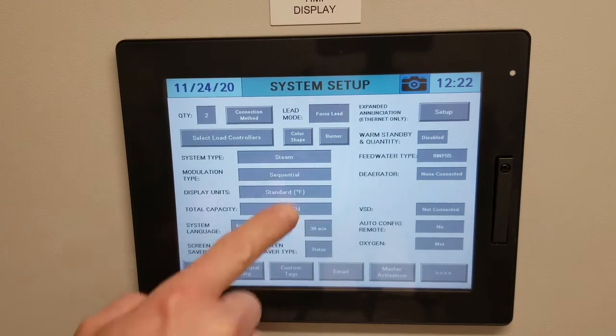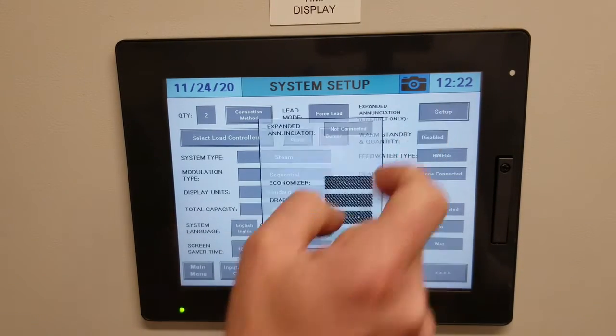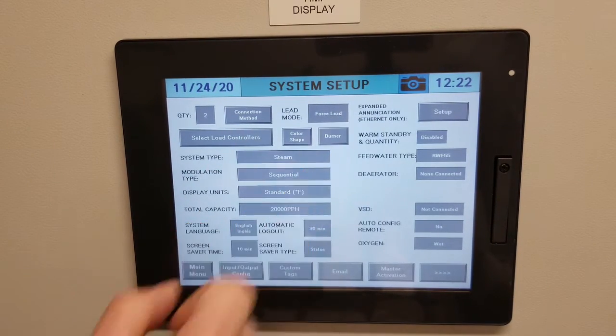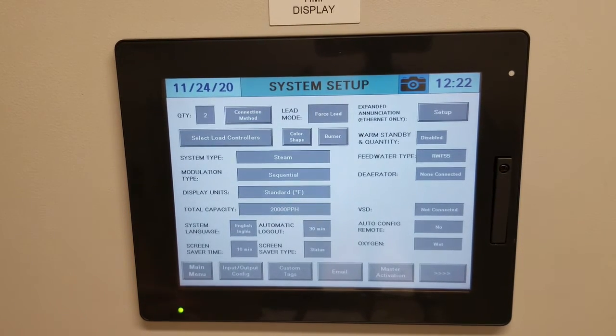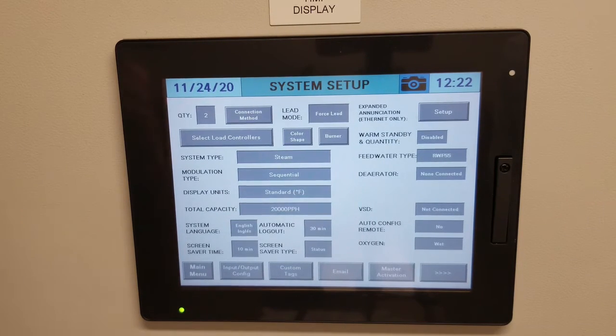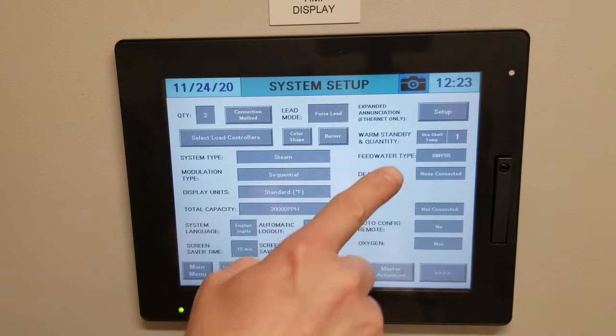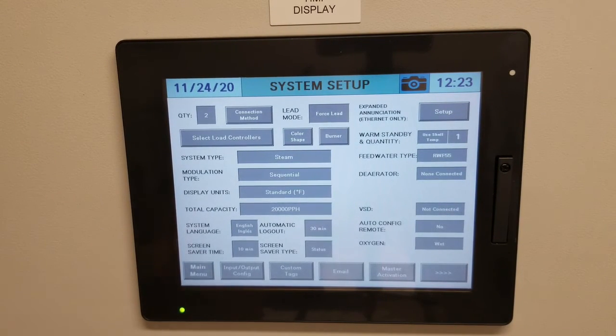On the right-hand side you'll notice an option for Expanded Annunciation. We do not have one on this job, but if you did, you would click on it to activate those options. Warm Standby works when you have local RTDs wired to the LMV system. If you have an Aquastat, you cannot use this feature. In our case we do have RTDs wired to it, so we enable this. You'll see it says 'use shell temperature' — that's why an RTD is required and not an Aquastat.